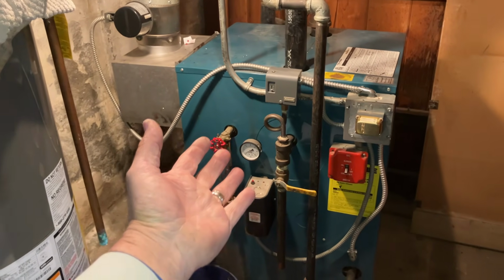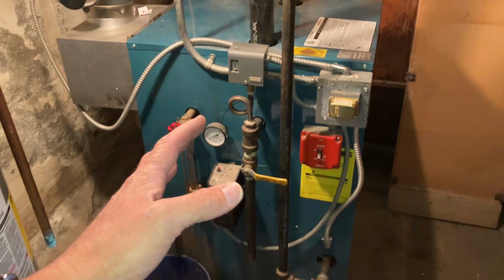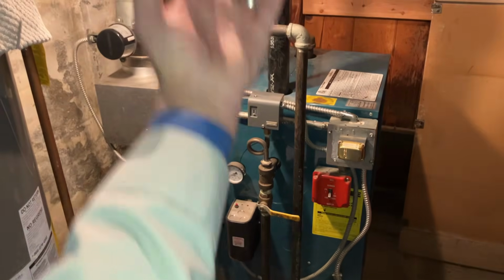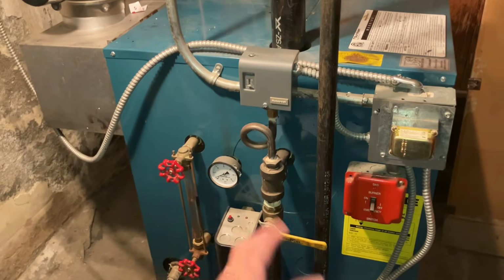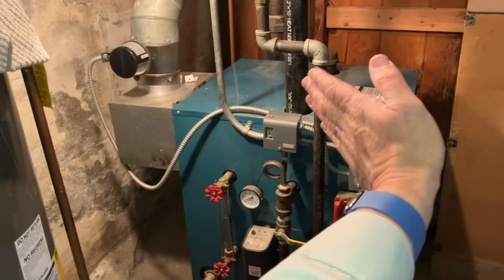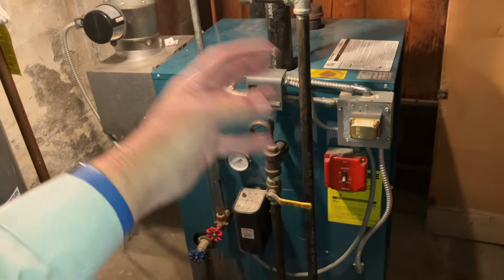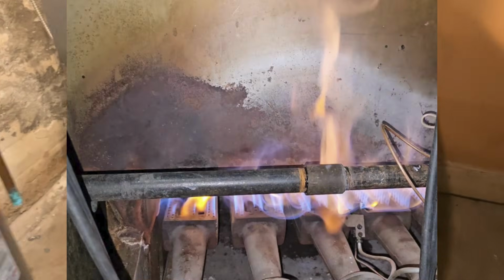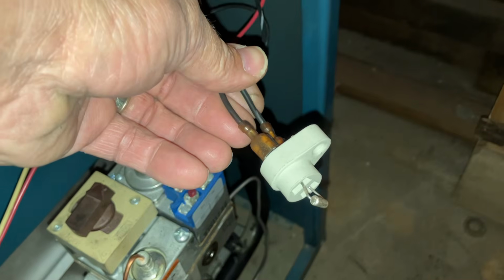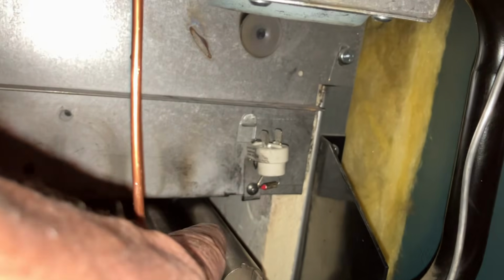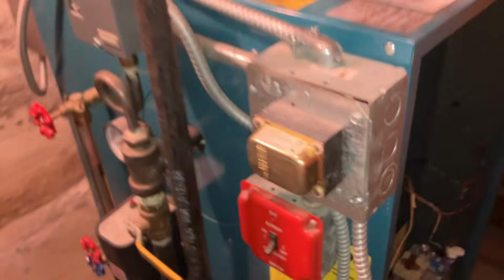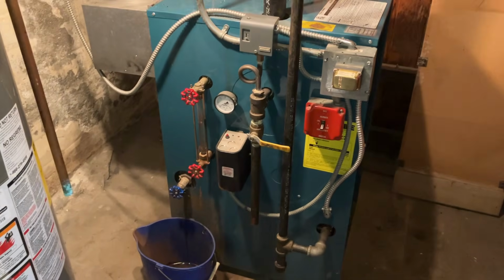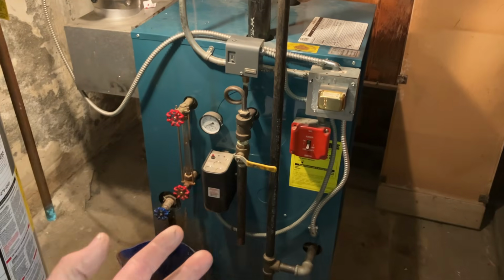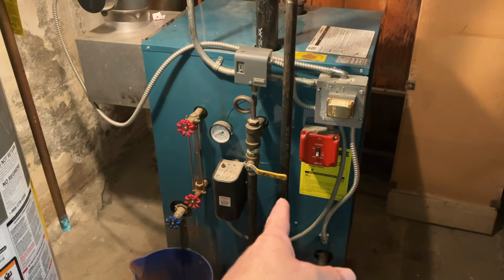In this particular case, you have all this soot building up on the bottom of the heat exchanger, and that's not good, because the heat and the flame is not going to be able to go up through the bottom of the cast iron block, up through the sections, heating the water. Instead, that carbon is going to be there and you're going to have flame rolling out. And hence, you have these safety switches like a flame rollout switch. And you can see burn mark there and another one over there. But when you have flame rollout, no bueno. And the only way to get rid of that is to scrub the boiler. And that's what we're going to do here today.